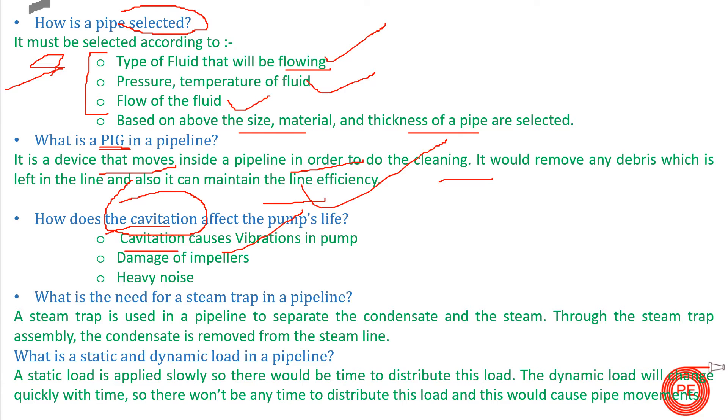It will damage your impellers because the oxygen bubbles will burst directly on the impellers and cause pitting, so you have to change the impellers repeatedly. There will be heavy noises because of uneven distribution of water and the bursting of bubbles inside the impeller. These are the three critically most important things which will occur when there is cavitation in your pumping system.